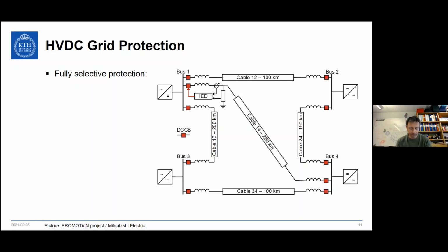I guess it doesn't have an impact on the initial incoming traveling wave. So the actual fault detection would be very similar, since that's mainly impacted by the length of the cable, how much a remote fault is dampened, and the line inductor used for the DCCB. So for the IED operating times, I don't expect the DC converter to make a big difference, but it might affect the DCCB design, depending on the control and how much energy is stored.